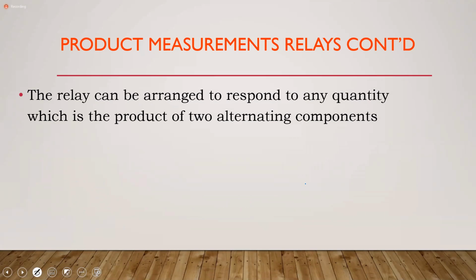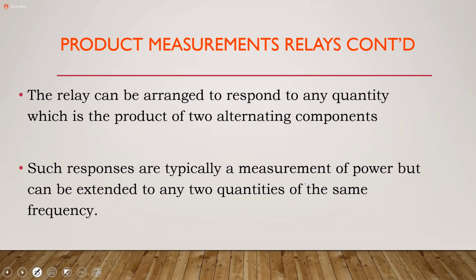So the relay, we can have it so that it will respond to any two quantities. Okay. And as I said, this can be based on calculating or determining power. In our case, energy, because the watt-hour meter is really measuring energy. But we can extend that to any two quantities of the same frequency. And it comes back to our knowledge of phasors. We can't add two phasors unless they have the same frequency. In the same way, we can't multiply these fluxes unless they have the same frequency. Okay?